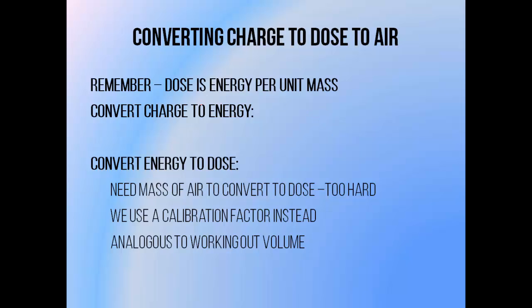Converting measured charge to energy absorbed within the chamber volume is theoretically quite simple. We multiply the measured charge by the known value of the average energy required to produce a certain amount of charge. This value is often written as W/e. The value that we've mostly agreed to use is 33.97 joules per coulomb. Multiplying these two values together gives us the energy.